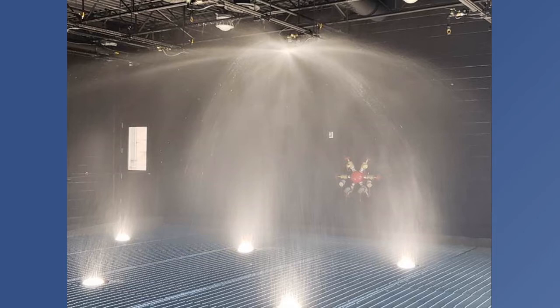Right, and that's based on the fact that in a residential occupancy, your fuel load is not necessarily directly below the sprinkler like it might be in a standard light hazard occupancy, but it's mostly out there on the perimeter. That's where you put furniture in a lot of residential arrangements. Exactly. So the life safety approach and a higher spray pattern, a higher wall wetting characteristic, is what differentiates the residential sprinkler from the standard spray.